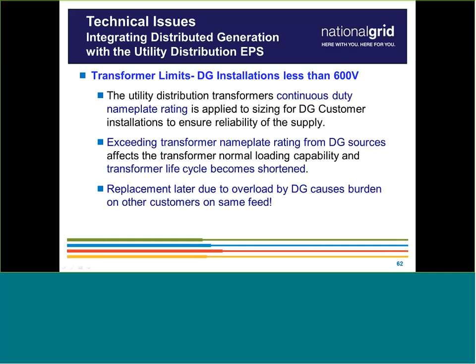What's your rule of thumb? Like, so you have a 100 or 50 kVA transformer. You don't even want to do 50 or 100 kilowatts, because you also have reactive power on it. So do you do like a 0.9 factor on it? I think where you can max load to? Yeah, I mean, usually we go with kilowatts. We can look at meter data. So I think usually we go up to the kVA value. Oh, you do? Okay. So that's pretty basic.